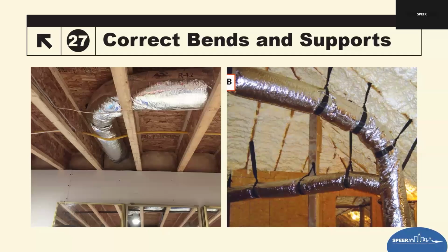So the one you see on the right-hand side basically has a 4-foot span. There's 2 there. These do have saddles. And then the one right in the middle is an additional one to actually support the sweeping bend instead of having sharp bends. The one on the left is just a sweeping bend in a floor system, which is correct and the right way to do that. Great examples that it can be done correctly and should be done correctly.